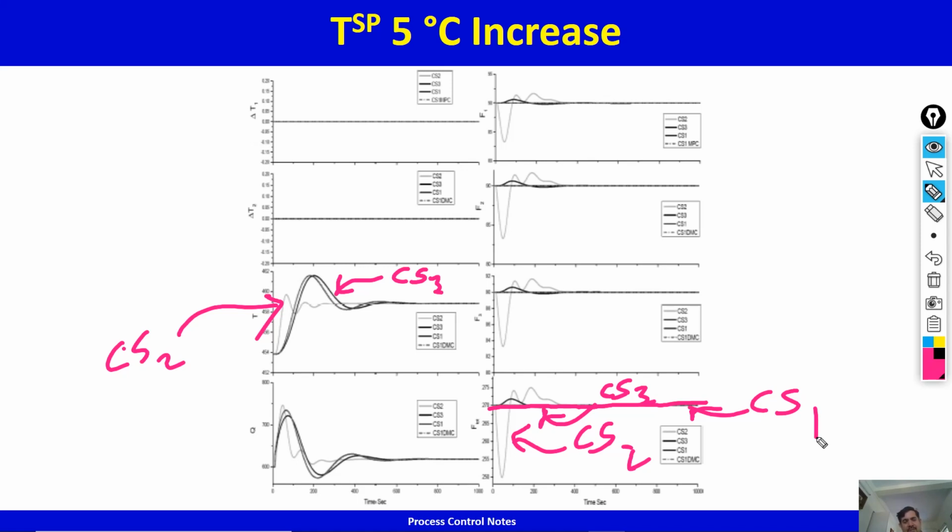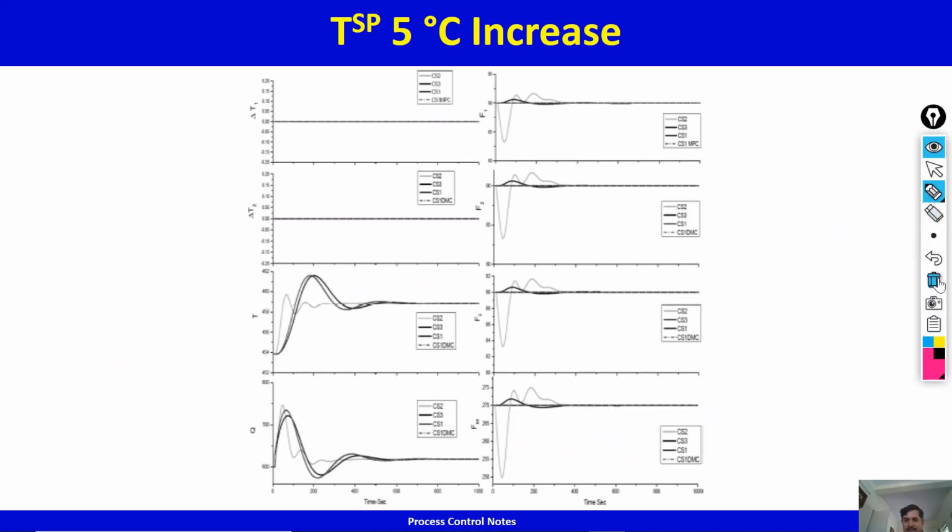DMC or no DMC is not making any difference, because delta T1 and delta T2 are essentially 0, and they are essentially 0 because each of the tubes is receiving the same heating rate. There is no pass heating rate imbalance. It's perfectly balanced. Now let's do some interesting things. It gets more interesting when you have pass imbalance in there.